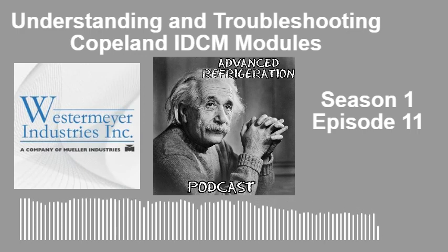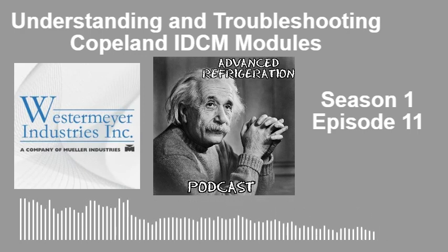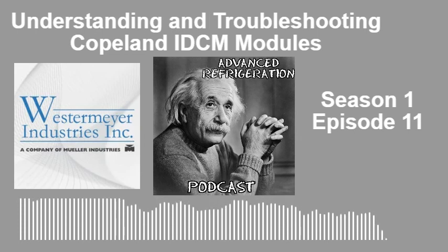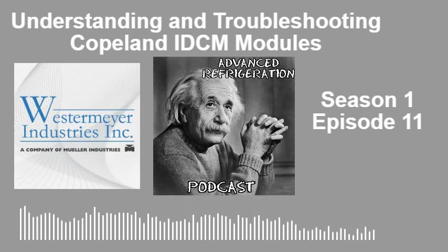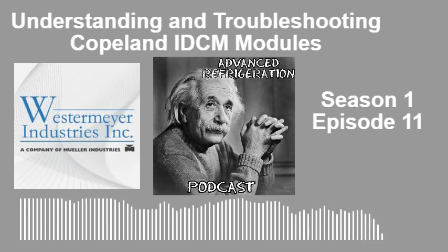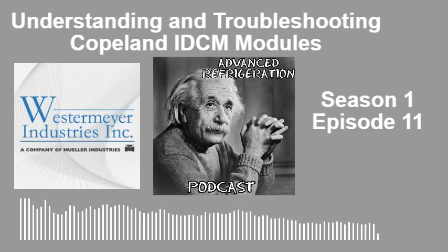You can still function. I remember telling you, this had to be at least 7 or 8 years ago. The condenser fan motors that have their own VFD per motor, I think all of them are now programmed at 0 volts and run 100%, but they used to not be. They used to be programmed where it was 100% at 10 volts. And I had lost an analog output module. This store was up in Connecticut. It was 63,000 square feet, one of the biggest, with at least 13 compressors on this rack.